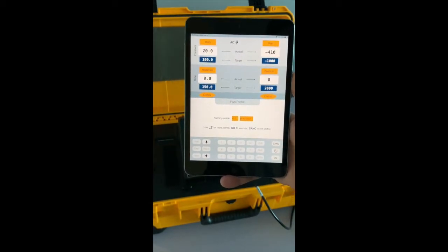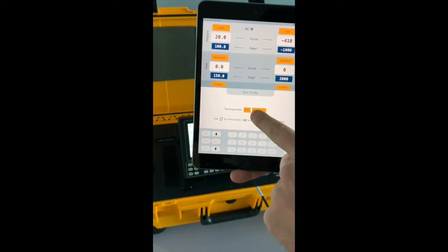the profile 15, step number 1. It will give me the name of that profile, so I make sure that whatever I'm entering is right. And then it will start populating the 4 target boxes here for the rates and for the actual values. And as usual, it's blinking, so it's gonna wait for me to confirm. As soon as I click on go, the test set will actually get to the desired target.